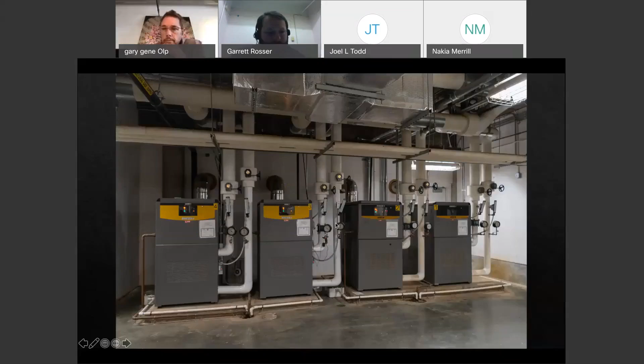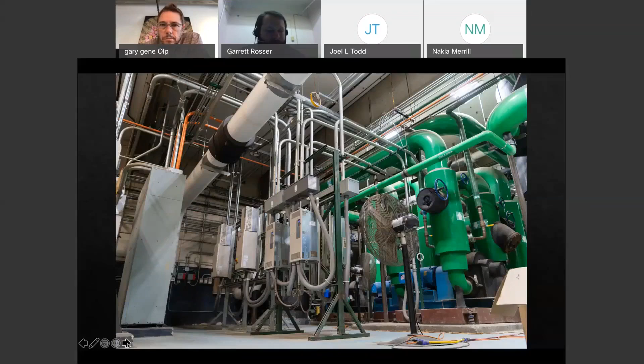We have seen inappropriate application of a VFD where the control is not really used in any beneficial way. That is that the motor may start up slowly, but then go to 100% capacity and stay at that level. That's not the purpose of the VFD, and you're really missing out on some opportunities there. So matching controls with the equipment is the best way to maximize that.